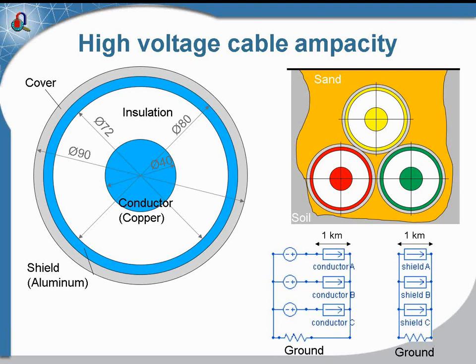What we know is the current flowing in the cable, but we do not know the current flowing in the shields. So the first task is to calculate the current in each element for the specific configuration of the three-phase cable, and the second step is to calculate temperatures.